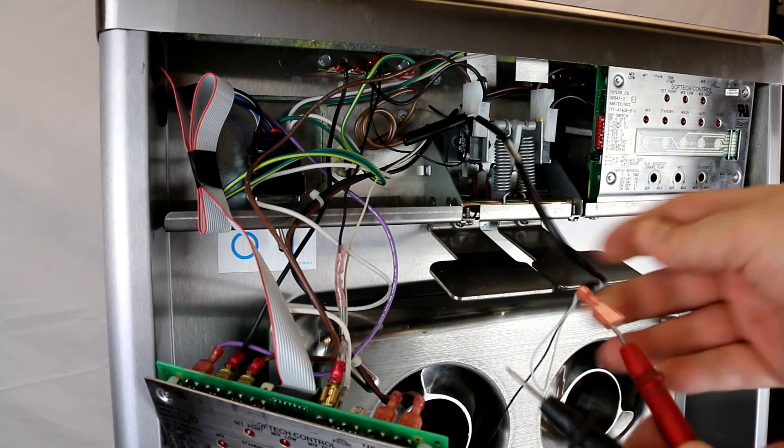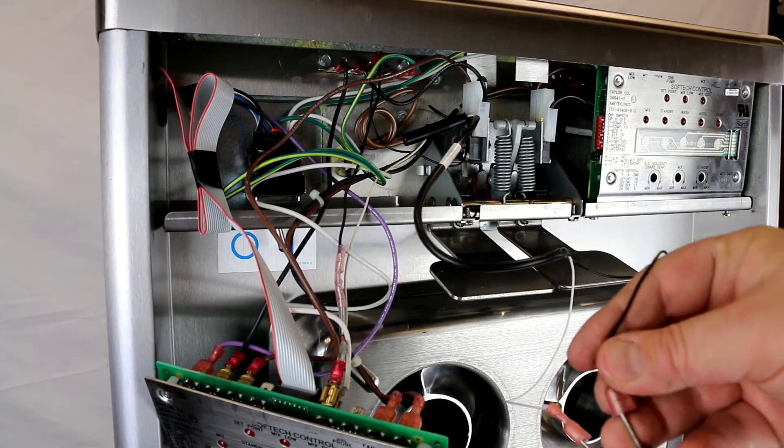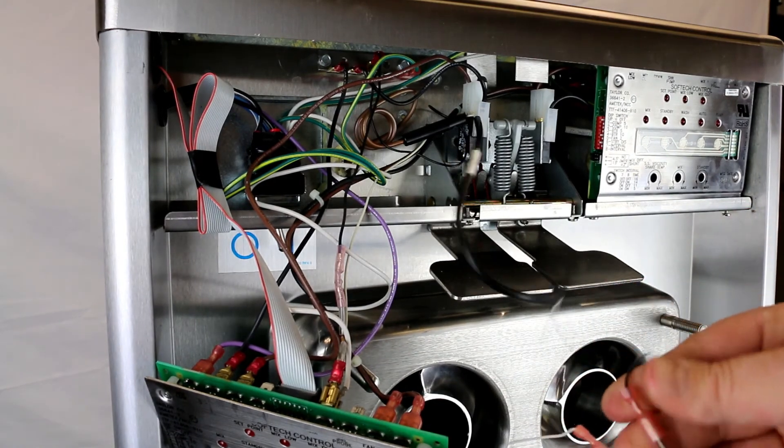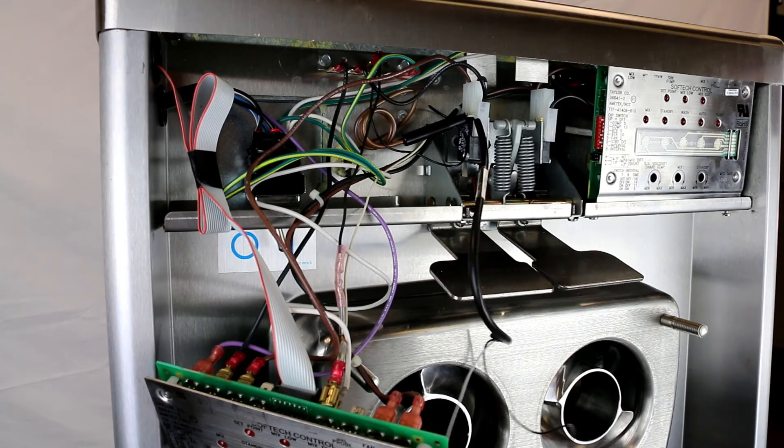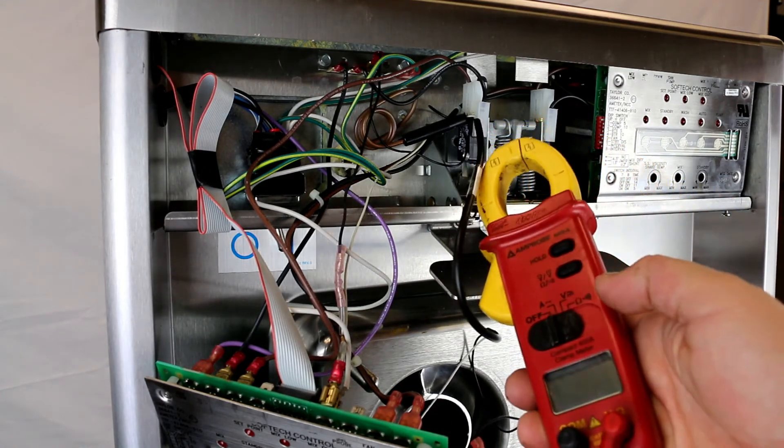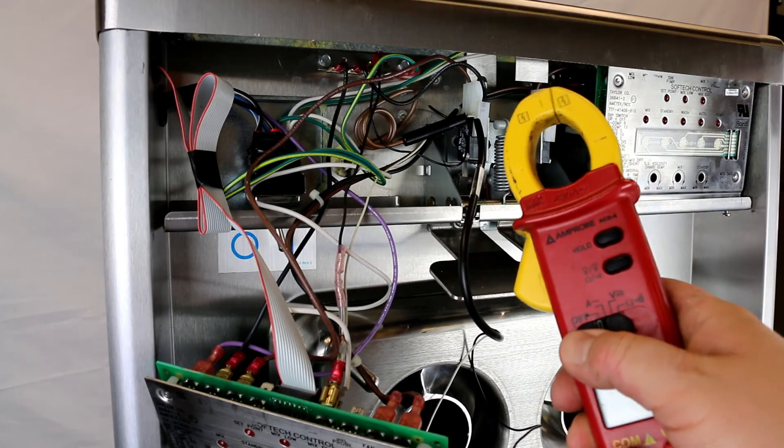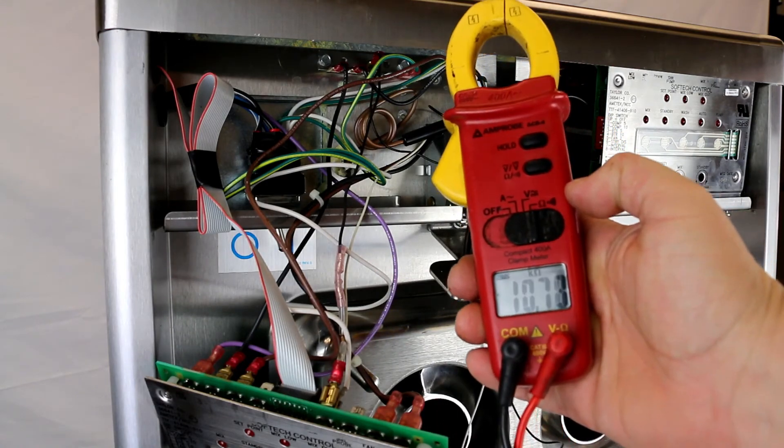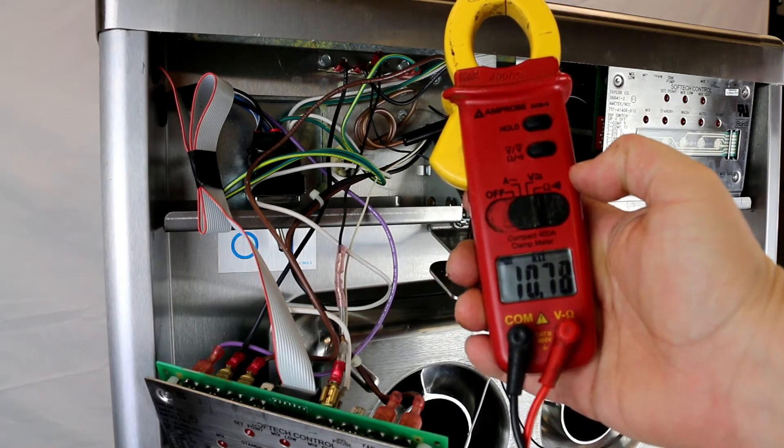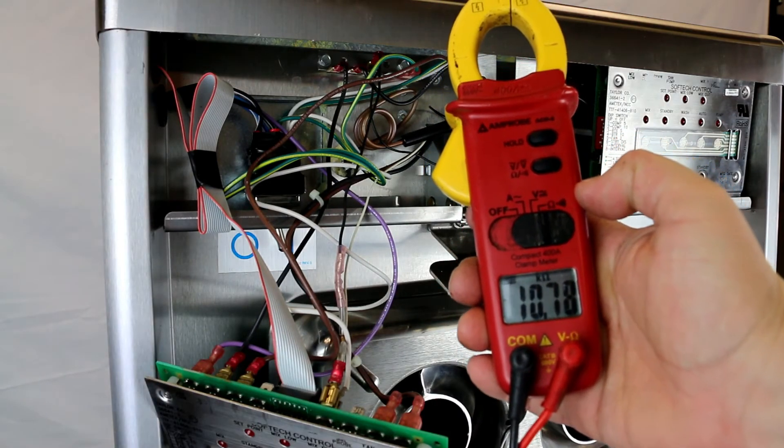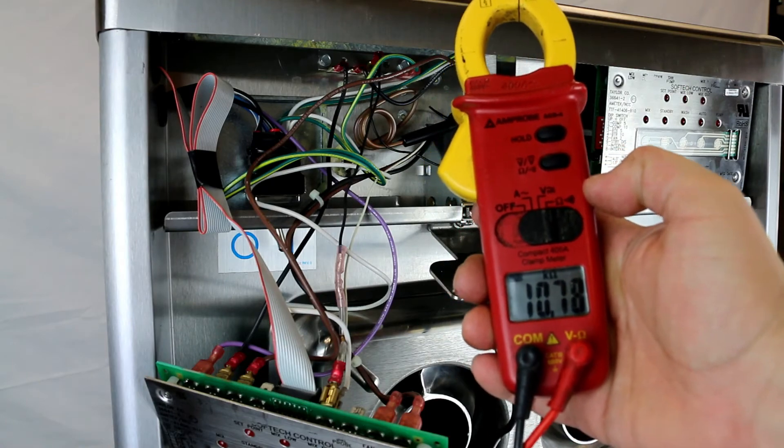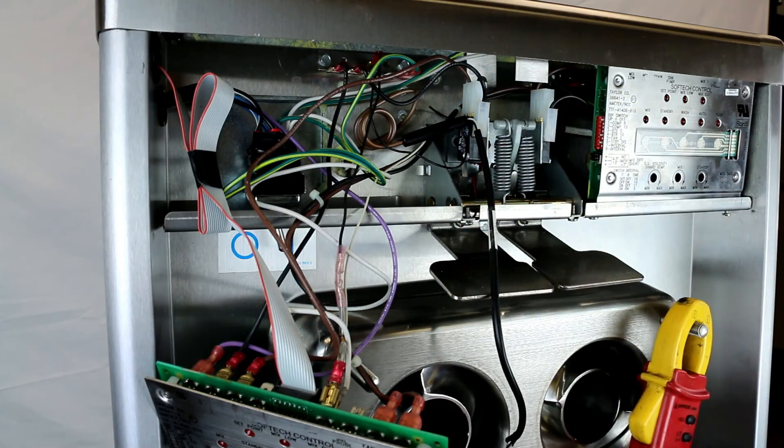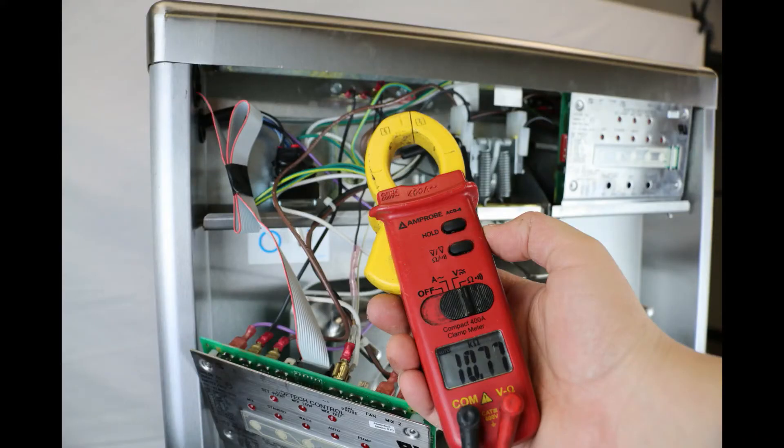You need to have a good connection there or else your meter could read OL. If you have a bad probe, your probe might also read OL or open. We have our leads connected, turn my meter to ohms, and it looks like we're measuring about 10.77, 10.78. Looks like it's settling at about 10.77, so we'll make note of that - the 10.77 ohms or 10.77K ohms.